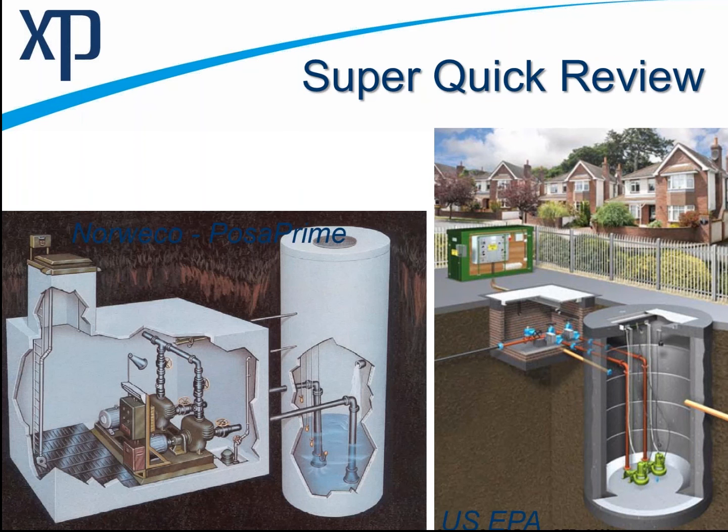The other common one is very similar, except we've moved what was a submersible pump. In this case, this is still a centrifugal pump, but we've now moved it into a dry pit area here. So whereas before the pump pulled directly from the water, now we actually have a suction line in, and we're pulling in. Otherwise, the same. The principal difference here is this is generally going to cost more and take more space to put everything this way, but it provides you easy access for any pump maintenance because you're right there. You're not having to pull a pump out of the wet well.